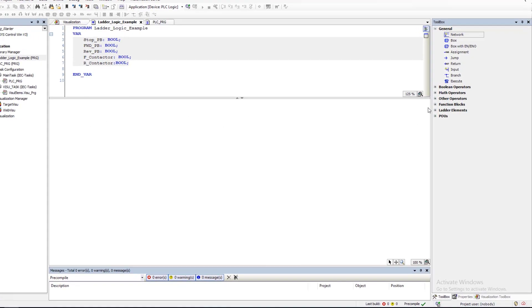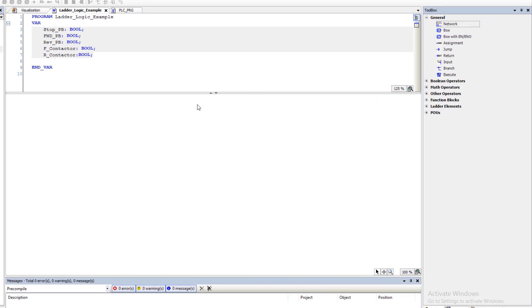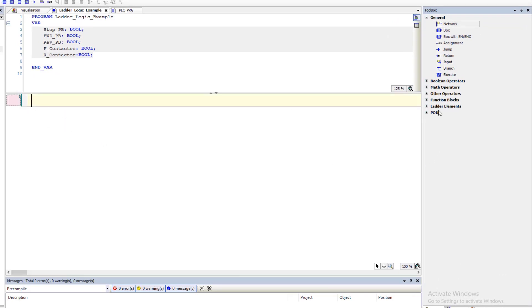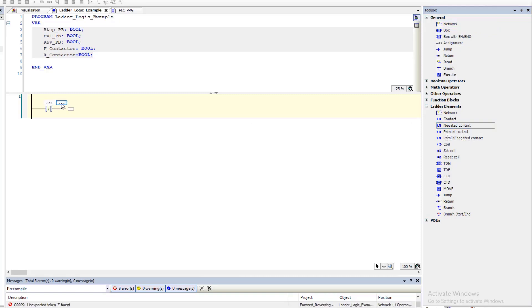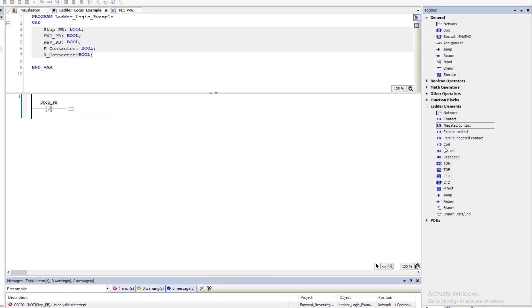We're going to come into our ladder logic and add a rung. We'll add a negated contact to begin with, and we're going to call this the stop push button. This is a forward and reversing starter, so we want it to act just like a real forward and reversing starter. We'll come in here and add in our coil.